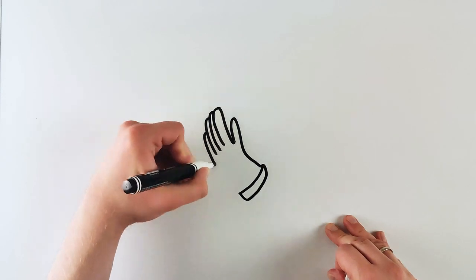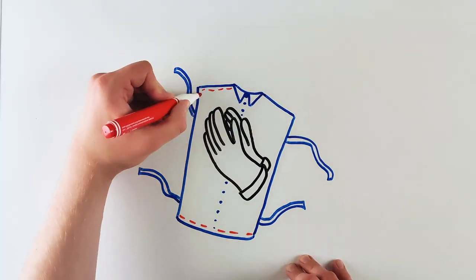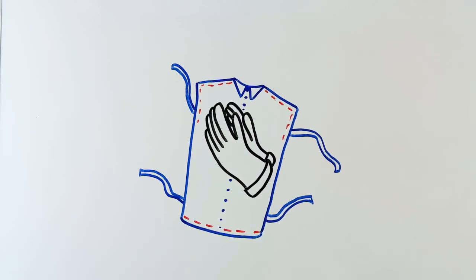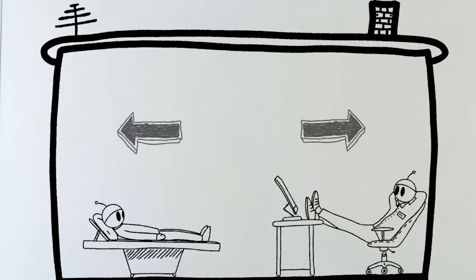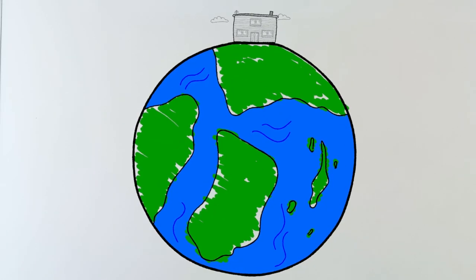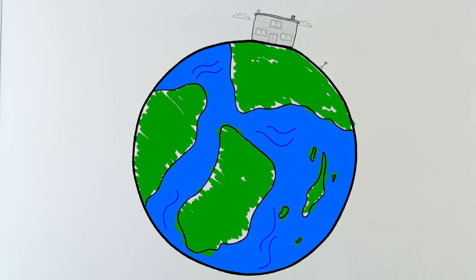Another means of protection is the aprons and gloves made of materials that absorb the radiation. But still, the most important and simplest way of protection is the distance. It is assumed the doctor should stay at least two meters away from the tube during the examination. But it does not mean he or she has to sit on the other side of the building.